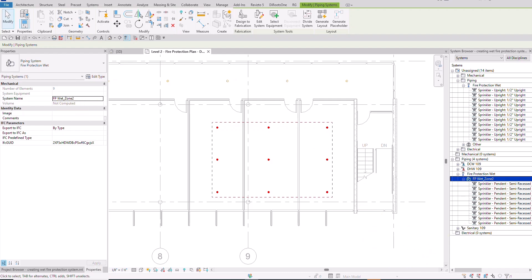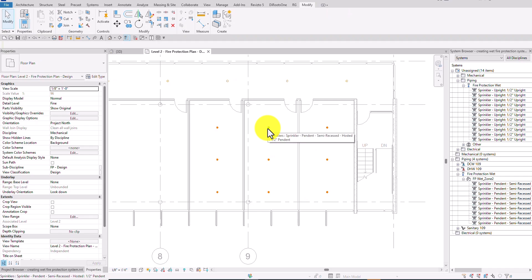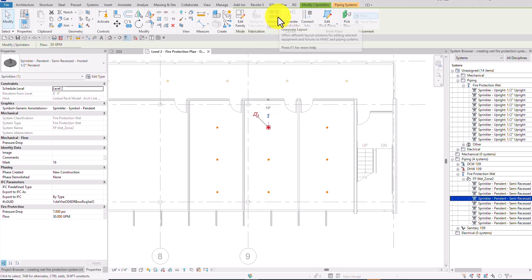Next I'm going to generate a layout to automate the pipe routing. I'll show how to do it manually later, but for now we'll do it automatically. I'll select one of the sprinklers that is part of the FP Wet Zone 2 system, then from the Layout panel I'll select Generate Layout and click it.